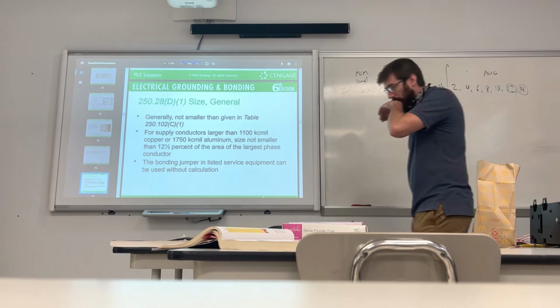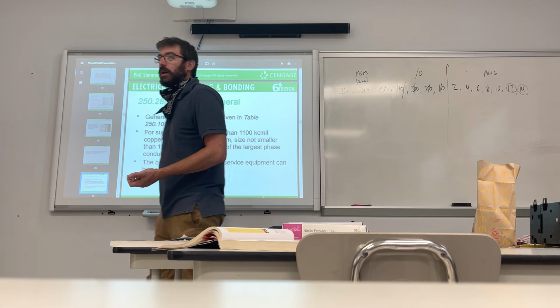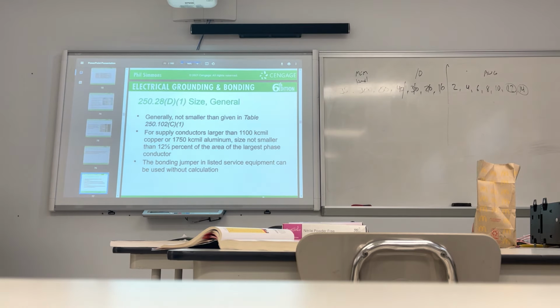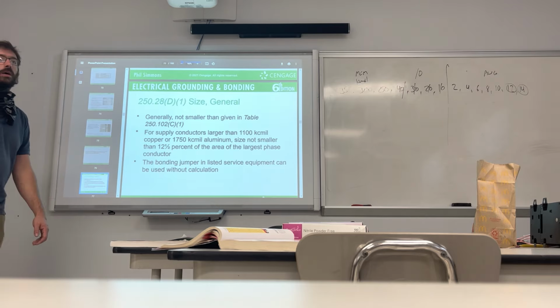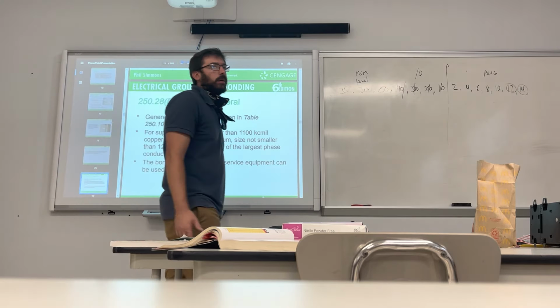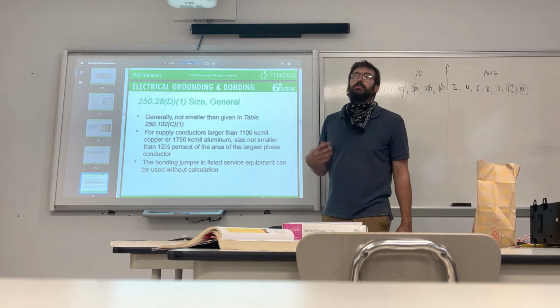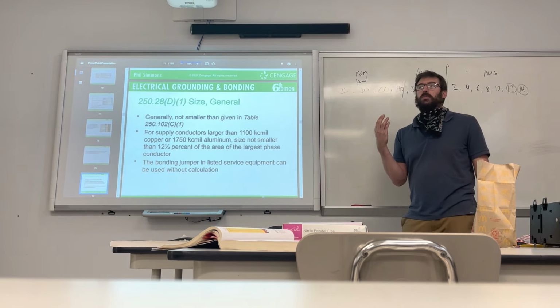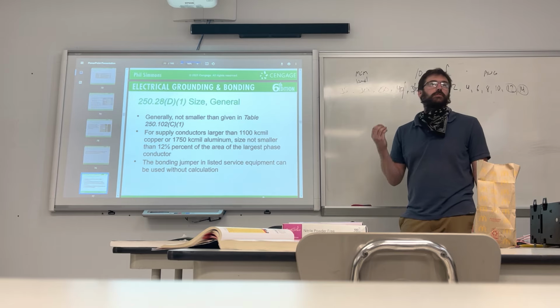Alright, so what are other acceptable ways? You can go with an acorn clamp. Could you go with a bolt and a nut and a crimp fitting? Could you crimp a hook onto the end of a 4-gauge wire, hook that around a bolt and tighten that bolt down onto some metal structure that's going down 10 feet in the ground? Could you do that? Absolutely. Could you do an exothermic weld? Can you physically weld or braze that pipe or that wire to something for a firm connection?